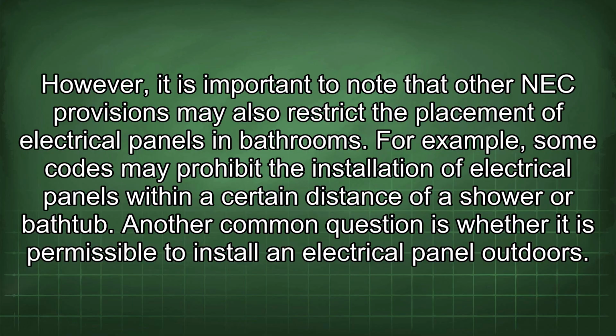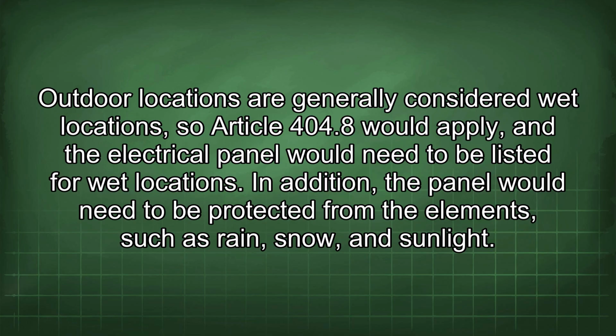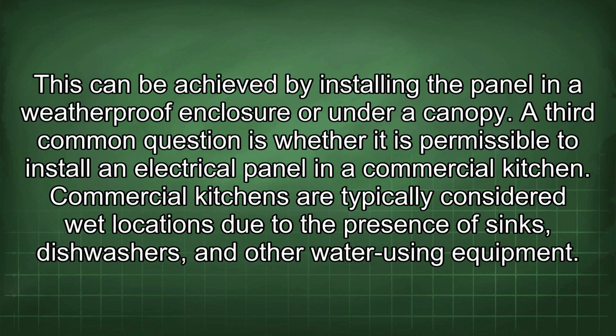Another common question is whether it is permissible to install an electrical panel outdoors. Outdoor locations are generally considered wet locations, so Article 404.8 would apply, and the electrical panel would need to be listed for wet locations. In addition, the panel would need to be protected from the elements such as rain, snow, and sunlight. This can be achieved by installing the panel in a weatherproof enclosure or under a canopy.